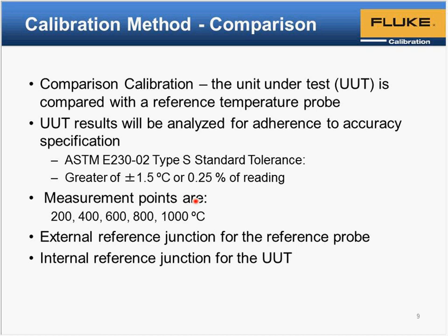A couple of other notes here. The reference probe will be using an external reference junction using an ice bath, which is traditional or typical for a reference thermocouple. But the UUT thermocouple does not have a reference junction attached, and the reference junction is actually inside of the readout.